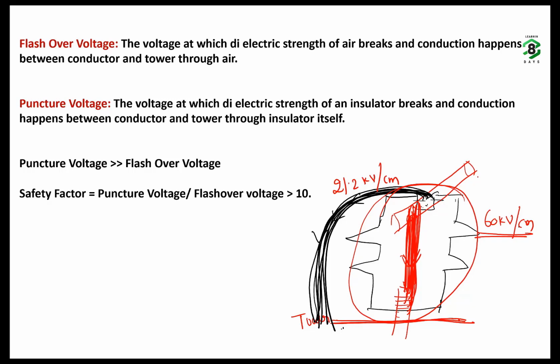Usually a safety factor we keep. Safety factor is the ratio of puncture voltage of the insulator divided by the flashover voltage. Greater is the safety factor, better is the insulation. Okay.